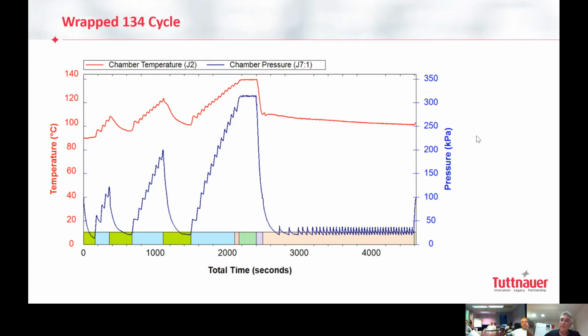It means we are now at 96. We have still 4%. And again, same concept. I take these 4% of air, molecules of air, or ping pong balls, which are in the room, and I will fill steam again. So I have a mix of 96% of steam, 4% of air. And then from this mix, it is split everywhere, right? Right. I will take again, remove again 80% of this mix. So after the third pulse, actually, I stayed with 0.8% of air. Why? Because 10% of 4 is 0.4. 20% of 4 is 0.8.